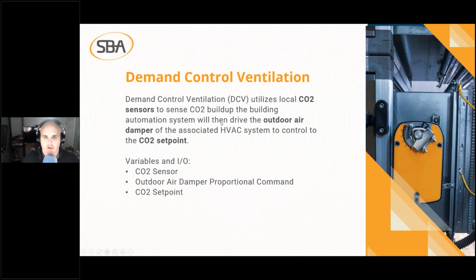So you sense the CO2 buildup, and then the building automation system, sometimes smart equipment, sometimes a building automation controller, is going to drive the outdoor air damper. This is a proportional damper, and this is a mixed air unit. This is not going to be 100% outdoor air, because if it's 100% outdoor air, then you're not doing any demand control ventilation on it. So you're going to have some proportional damper on a mixed air unit, and that proportional damper is going to be opposed to the return air dampers. So they're going to have an inverse signal command.